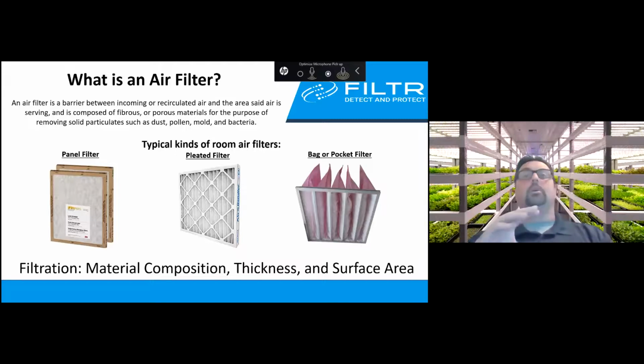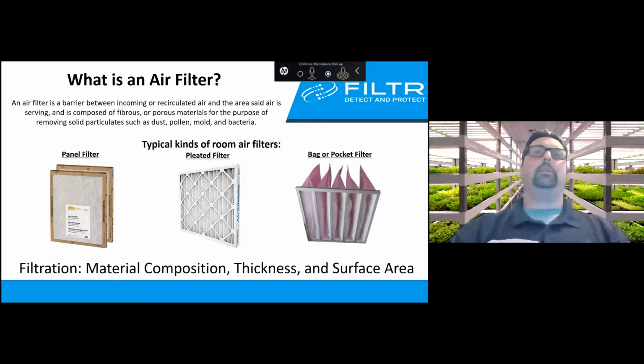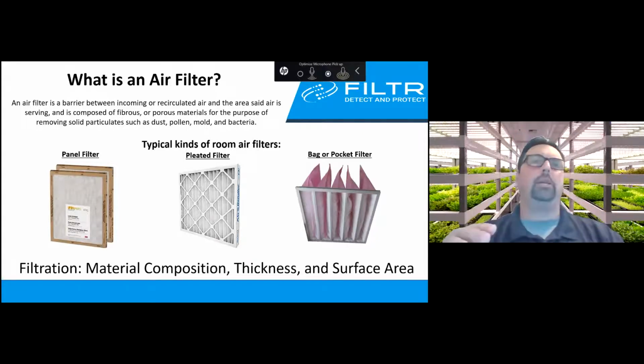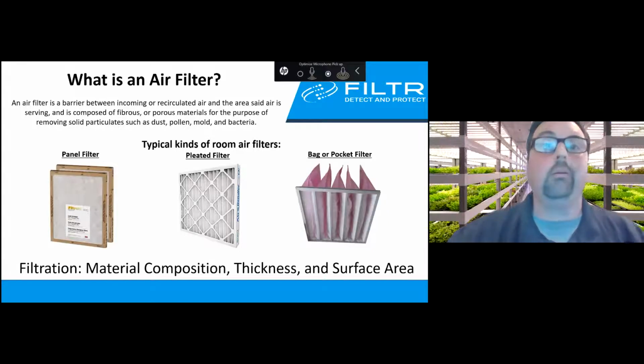Some HVAC systems, depending on size or manufacturer, have what's called a bag or pocket filter, which acts similarly to a pleated filter by providing more surface area. The key takeaways for a filter cartridge are the material composition, the thickness of the media, and the amount of surface area available to catch particles.